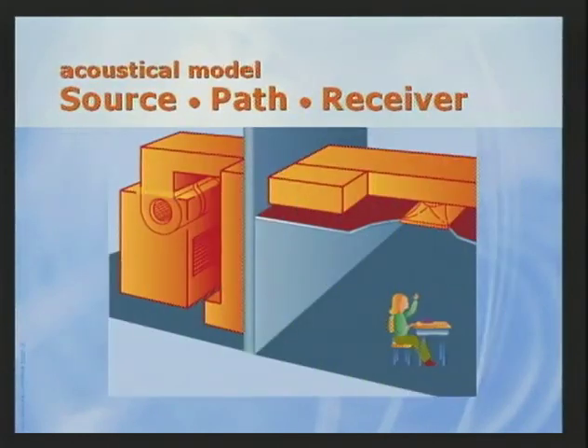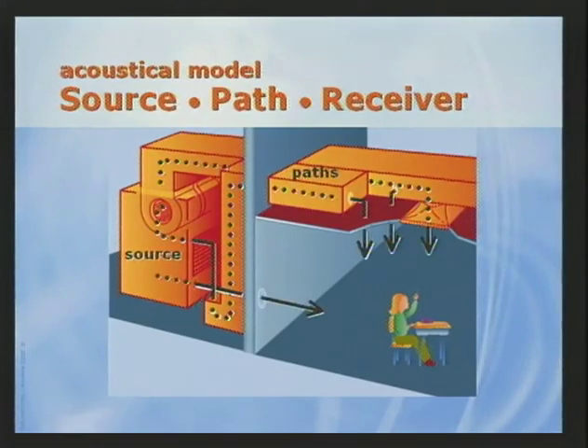For each of these categories, we can apply the source path receiver model. This method of modeling breaks the sound from the source into separate paths. Each path starts with the sound power data of the source, contains corrections for each element the sound encounters as it travels from the source to the receiver, and ends in a room correction, which accounts for the acoustical characteristics of the room. In this case, the receiver room is a 30 by 32 by 9-foot classroom that has an acoustical tile ceiling, and the receiver is a student sitting 6 feet from where the sound enters the room.